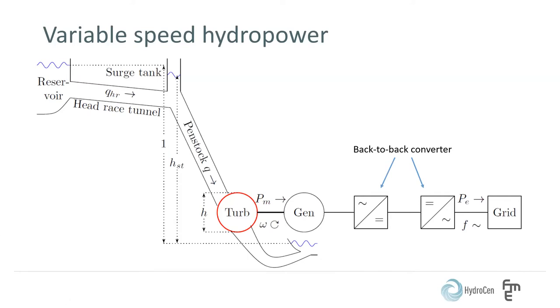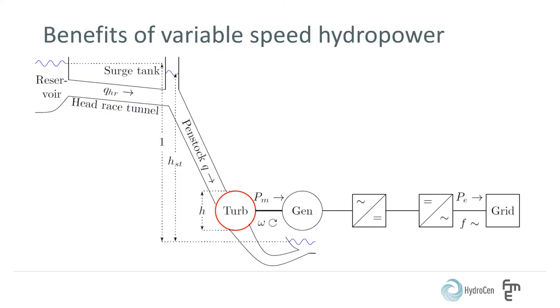Since we have utilized a conventional synchronous generator, we are able to bypass the converter if we want or need it. The main benefit of variable speed hydropower is that the turbine can achieve a higher efficiency when not operating at its best operation point, since the rotational speed can be changed.